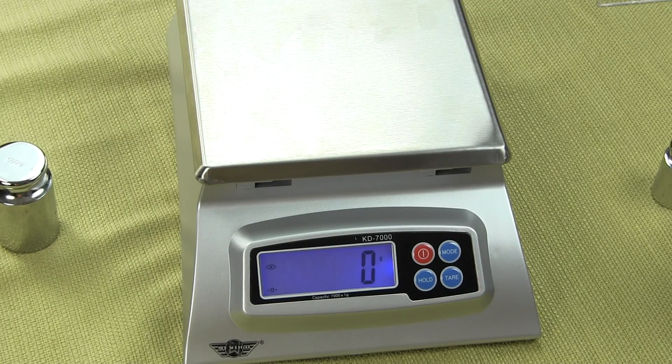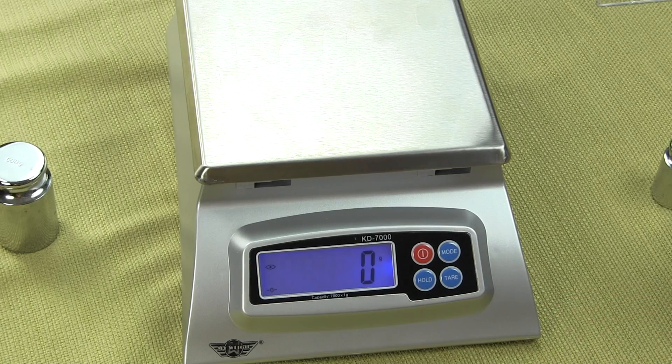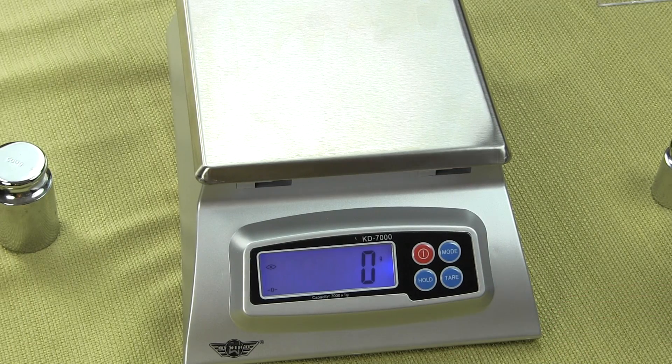The cal mass is optional and you need five kilograms. If we tried to calibrate the scale with 500 grams, it's not going to work — it is specific. It must be five kilograms.